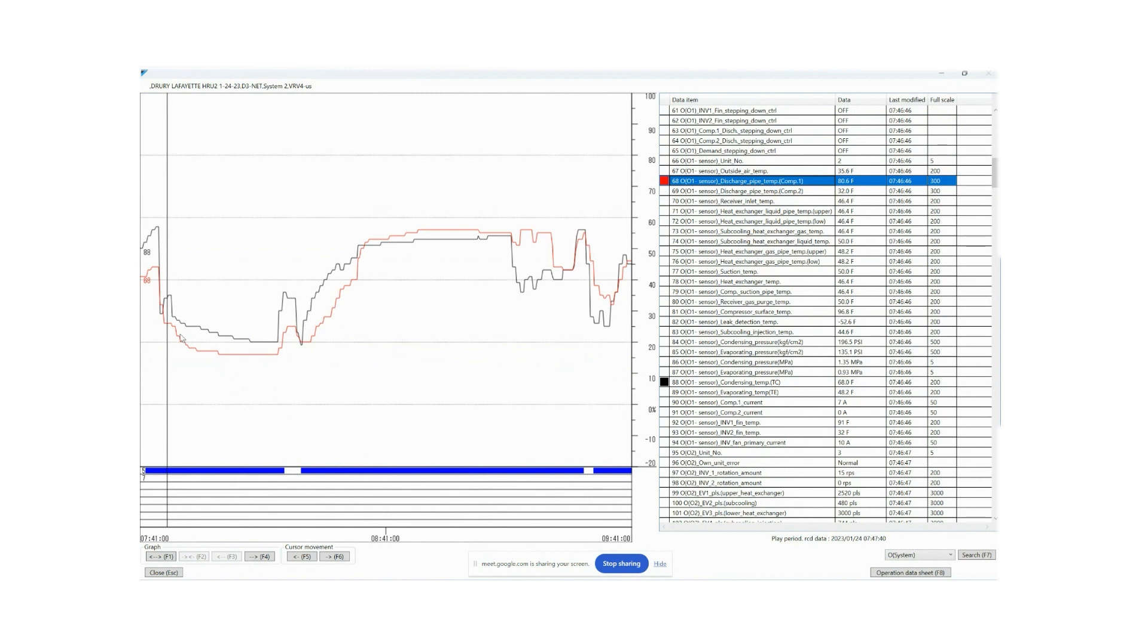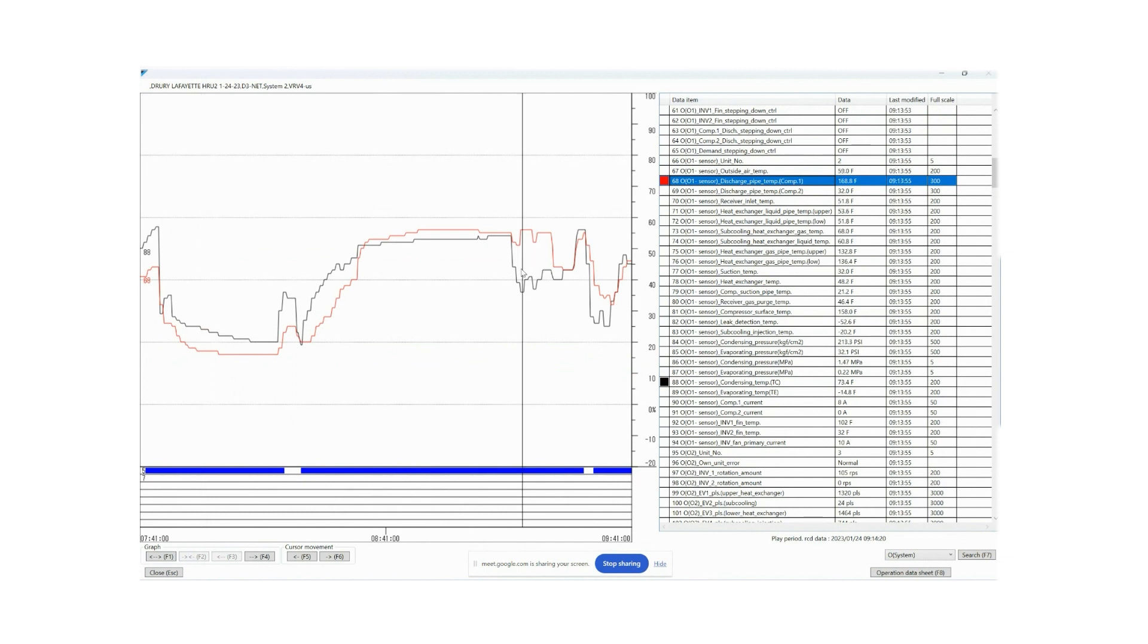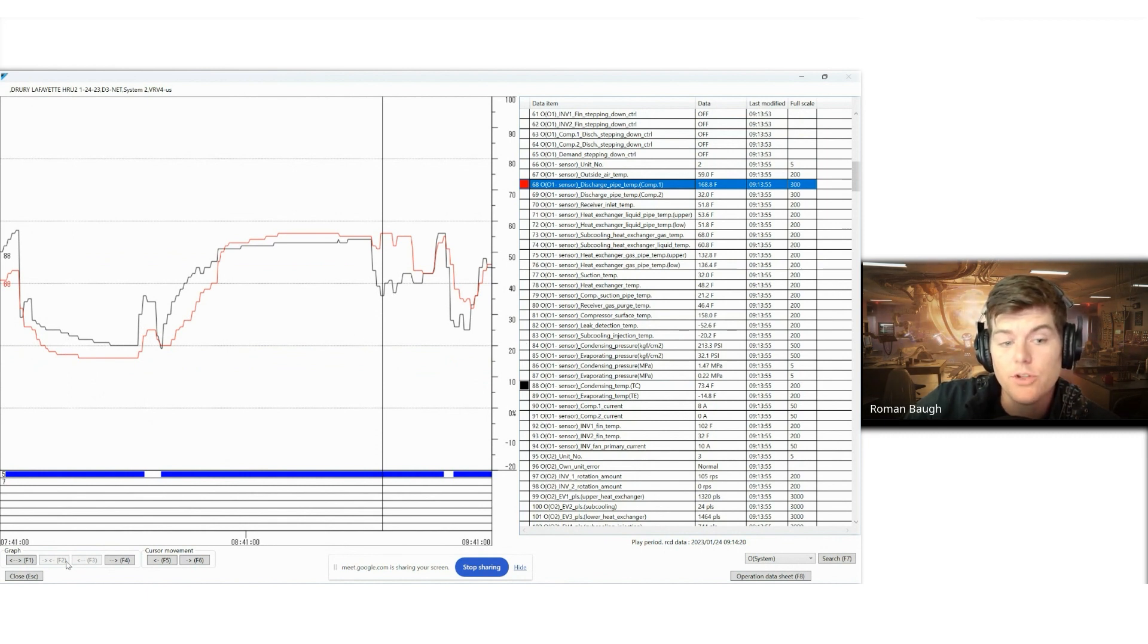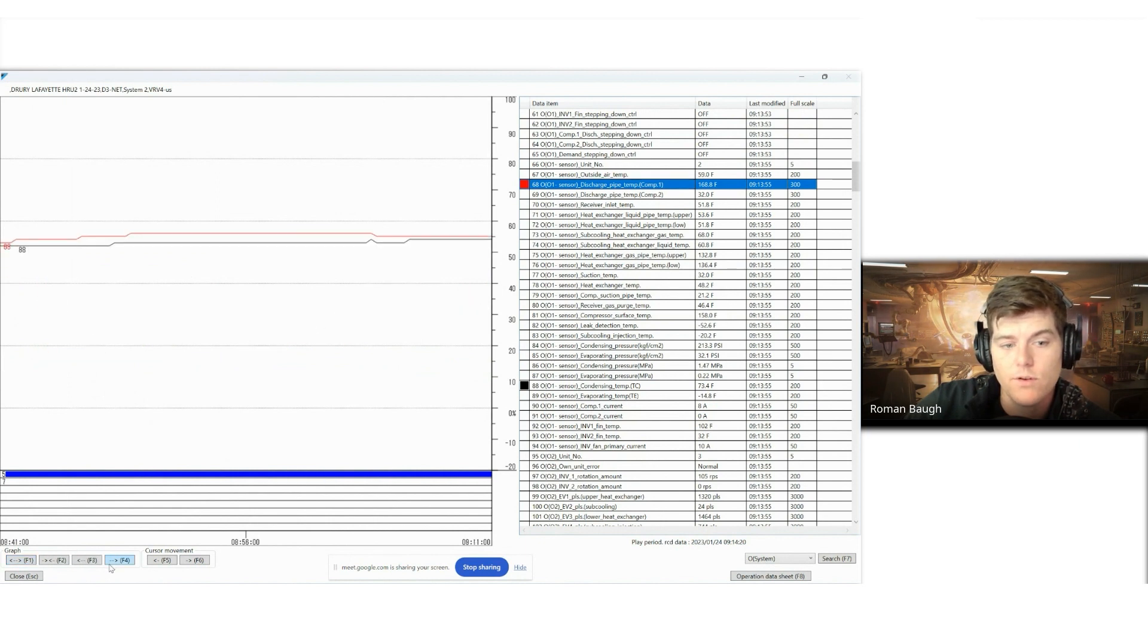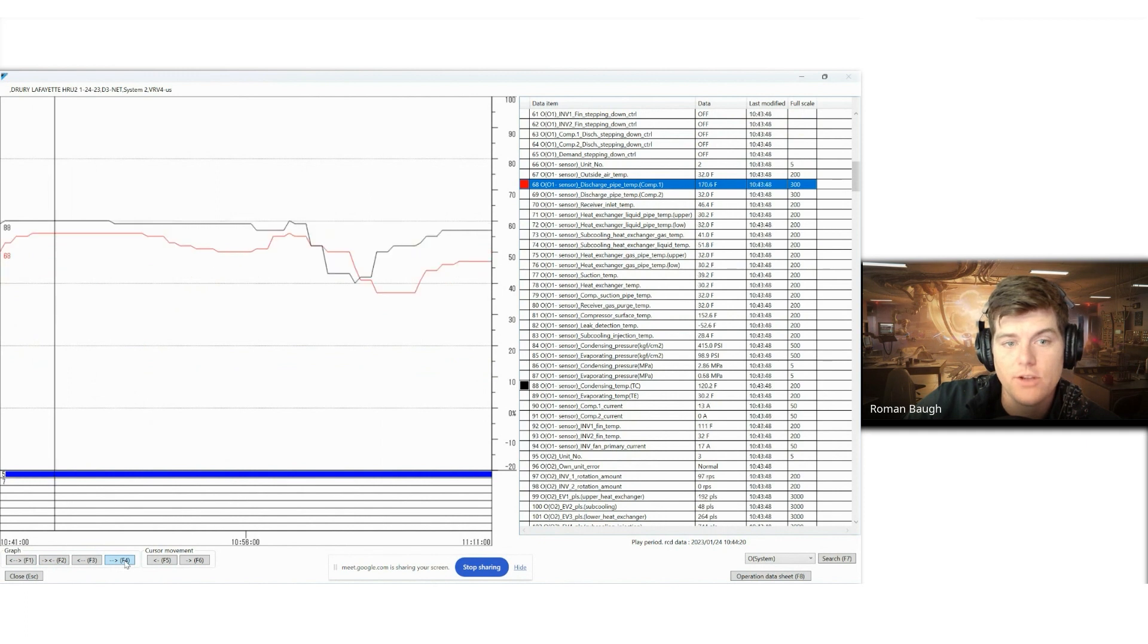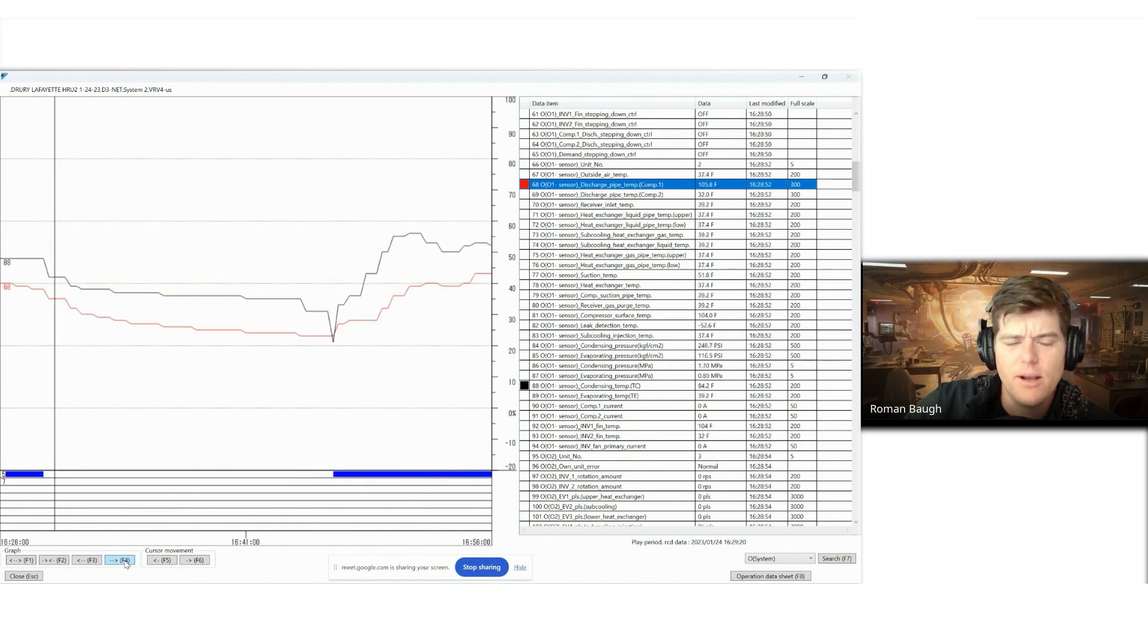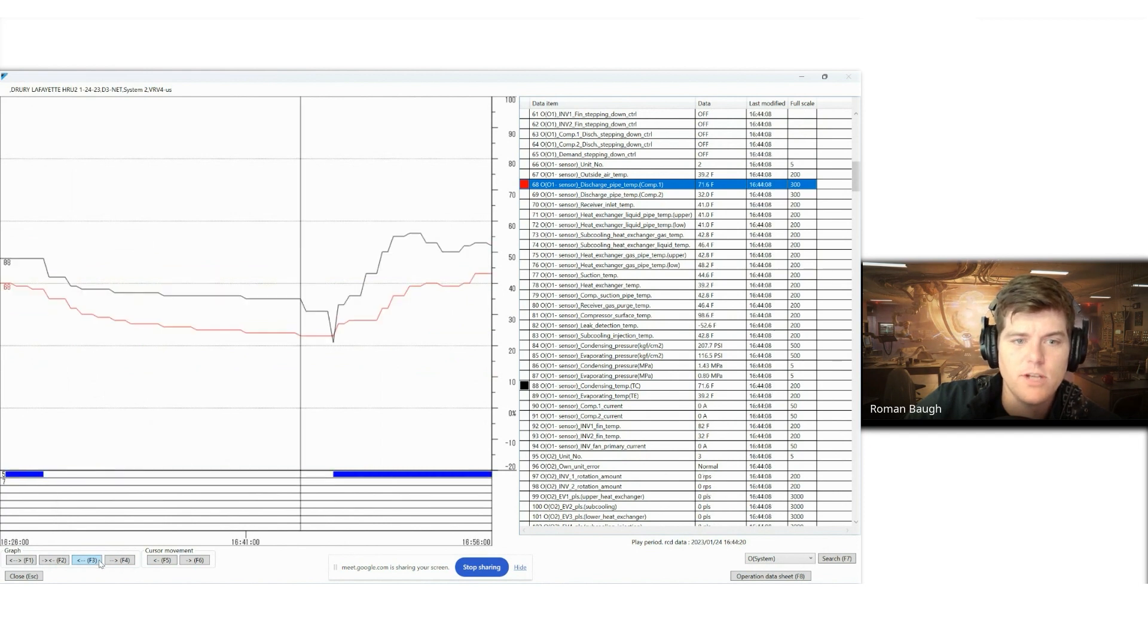You can see as it ebbs and flows, as they fall apart. You'll notice here is probably the greatest distance between the two, possibly even here. I can click on that and I can say, in this two hour window right here is my greatest discharge superheat. And then I would do the math. So then maybe I want to zoom in more on that section. I would then click the F1. I would go over to that timestamp to see why was it so far apart? What else was going on in that area? How quickly did it change over time?